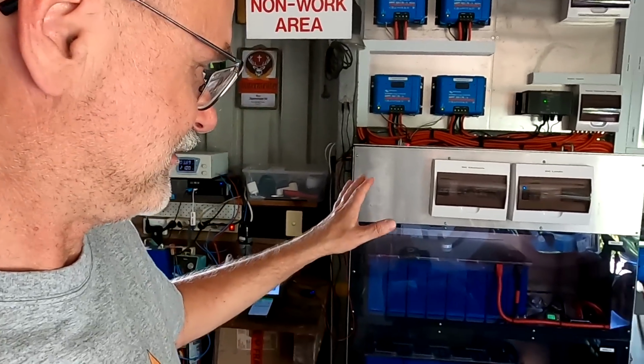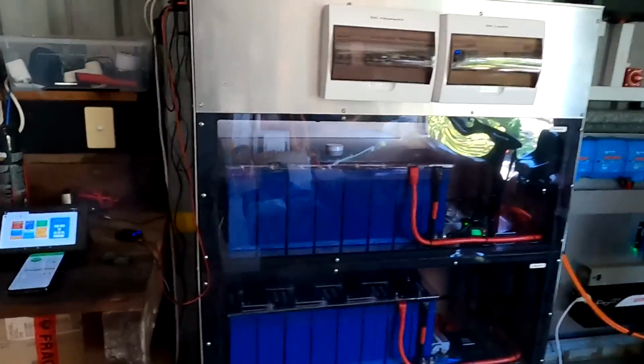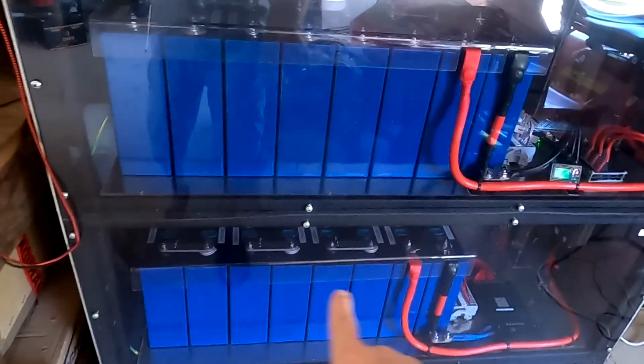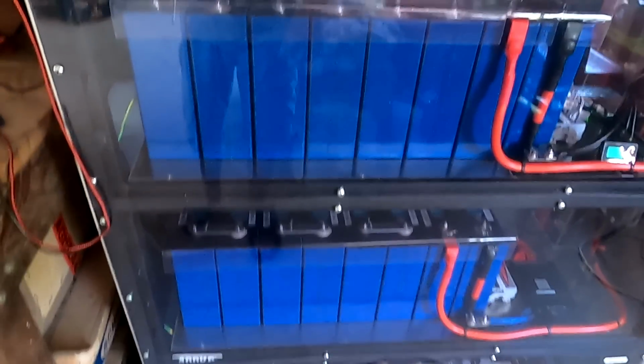So yeah, anyway, so far this little stress test here of our 3 battery banks. I think we have to do some maintenance work, some measurement here on the middle shelf battery with the aluminium bus bars, and measure the impedance including the bus bars and the terminals for each of these battery cells, and see what we can find. Maybe there are some higher resistances somewhere between bus bar and terminal, so we need to find them and improve the situation of this battery again.